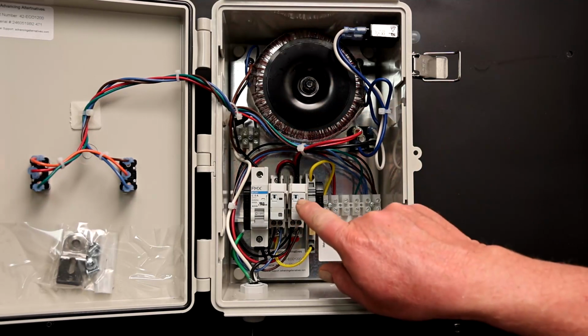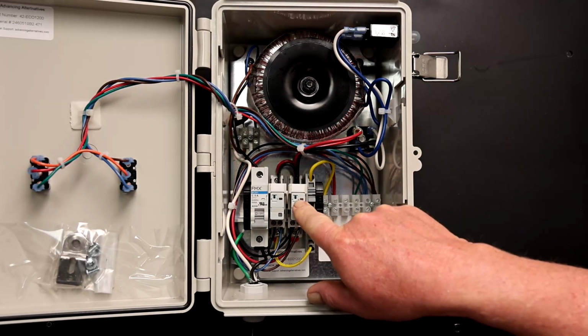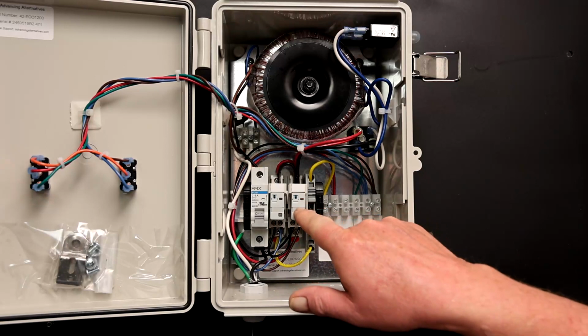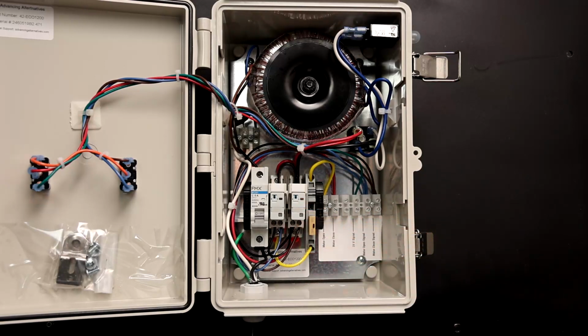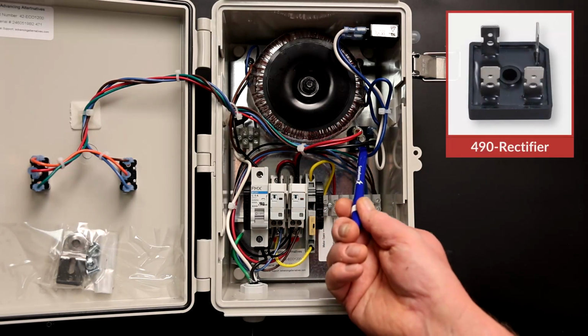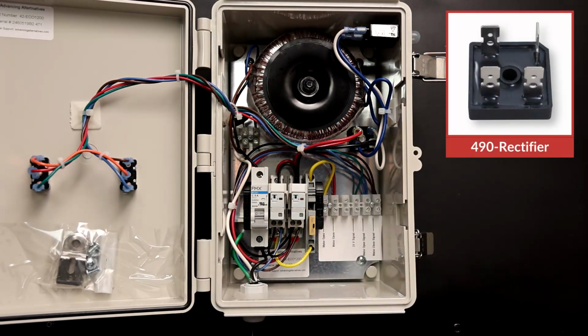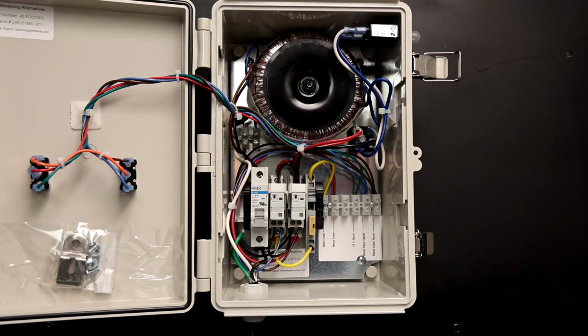When a relay is engaged, it has a green LED light that illuminates. If the light is illuminated and the motor is not running, there's a good chance that the relay has gone bad. The DC rectifier is located here. A loss of the 24 volts completely is usually a sign of a bad rectifier. It can be replaced without too much trouble.